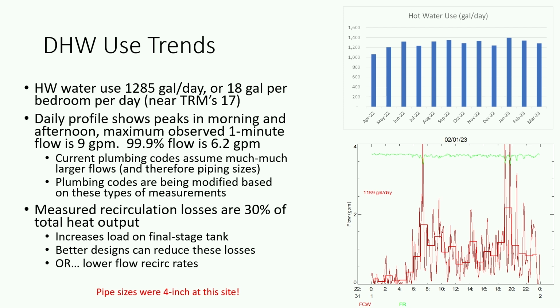One thing that we found is that some of the ASHRAE guidance on peak flow rates in terms of gallons per minute implies what you use to size piping. So the incoming cold water pipe on the hot water system was a 4-inch line. And I know because I had to spend a lot of money for a flow meter to fit that line. But what we found is that 99.9% of the time, the flow was below 6.2 GPM. And so that's 10 times lower than some of the ASHRAE guidance would predict.